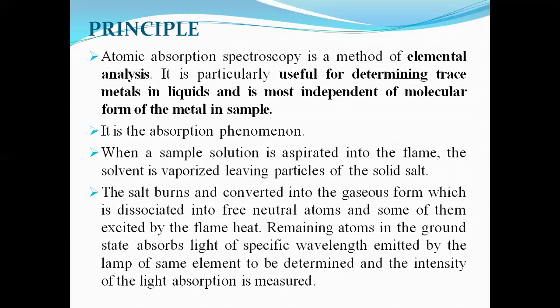In this technique, there is a light source — a radiation source — and we supply our sample through the flame. The flame temperature vaporizes the solvent used to dissolve our sample. Once the solvent is vaporized, solid salt particles remain. This salt burns and converts into gaseous form, dissociated into free neutral atoms by the flame temperature. Some atoms move to the excited state, while the remaining atoms in the ground state absorb light of specific wavelength from the radiation source, and this absorption is measured by the detector.